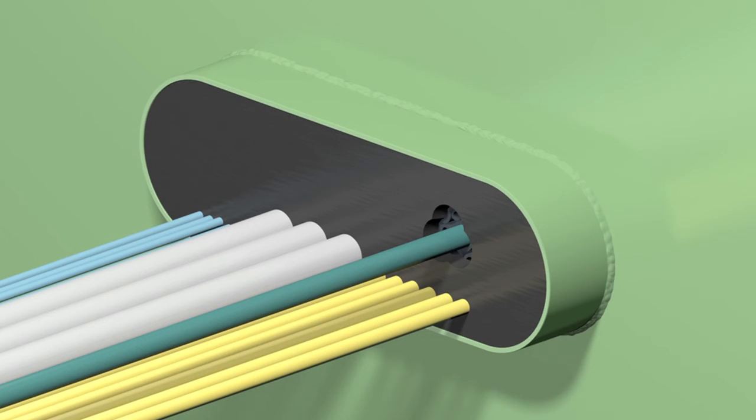Clean and dry the newly ducted cable thoroughly and refill the opening in the sealant layer at both sides of the transit with FIWA sealant. Finish the new sealant layer in the same way as done for the initial sealant layer.